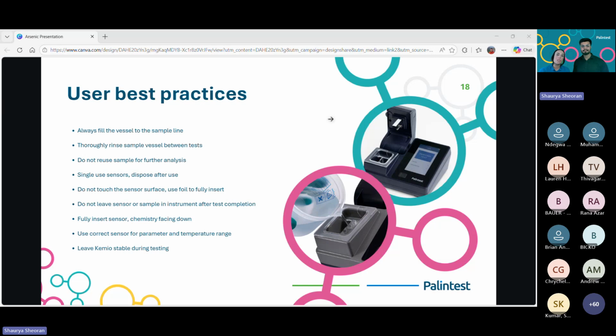Thoroughly rinse the sample vessel between tests. This is to make sure nothing from tests beforehand, or anything that may have landed in that sample vessel between tests, can cause interference. Do not reuse the sample or the sensor for further analysis. Once the sensor has made contact with the sample, the chemistry is already in there. So both need to be removed and replaced, with a fresh sample and sensor for every test.